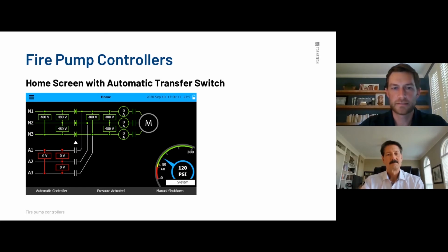And also, again, this is all set up. You can see here, this one's automatic, pressure actuated, and this one has the manual shutdown. So we're on the one without it; it was set up to say automatic shutdown. You can see what it would say if it was a manual shutdown. That's how it's shipped from the factory, is manual.